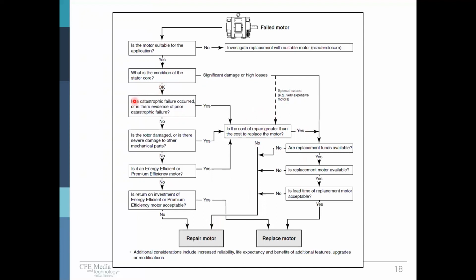Going back to our left side, after we've assessed that core, we go through what about a catastrophic failure, or evidence of prior catastrophic failure that's made worse by this failure. Significant damage, again, evaluate cost of repair versus replace. Damage to the rotor, again, cost of repair versus replace. And as I mentioned about any smaller machine, a NEMA style frame motor up to maybe 1 or 2 or even 300 horsepower, if there's significant damage to the rotor, it's probably going to move into replace rather than repair mode, unless it's a special motor or the delivery time is way too long.